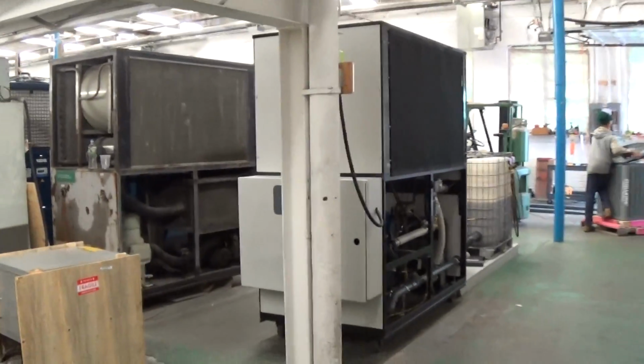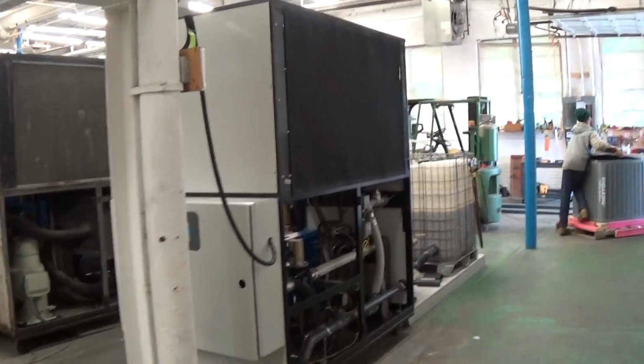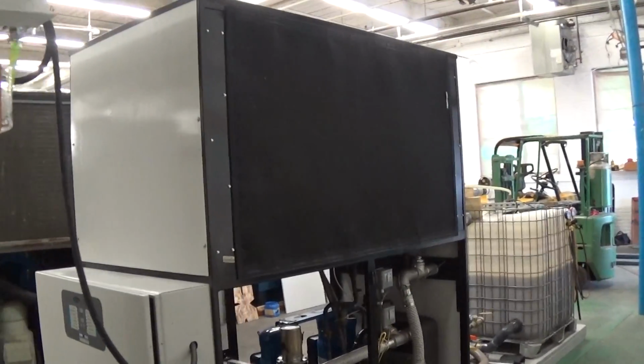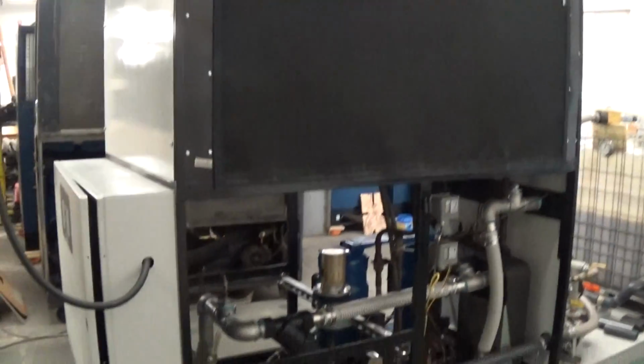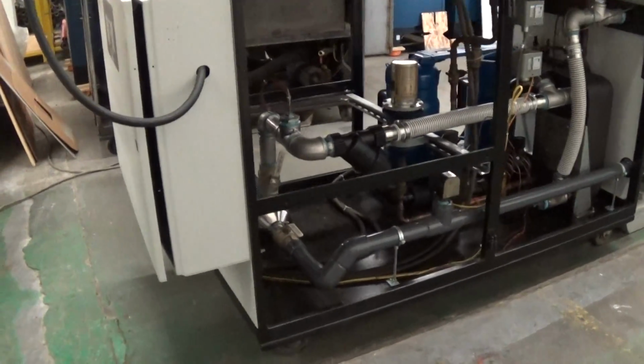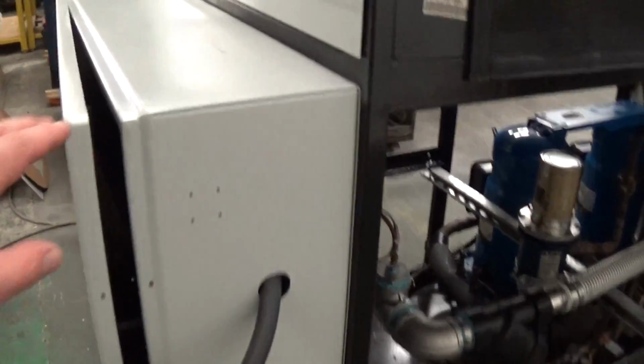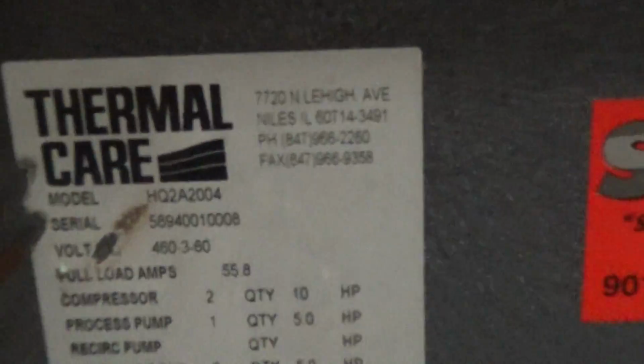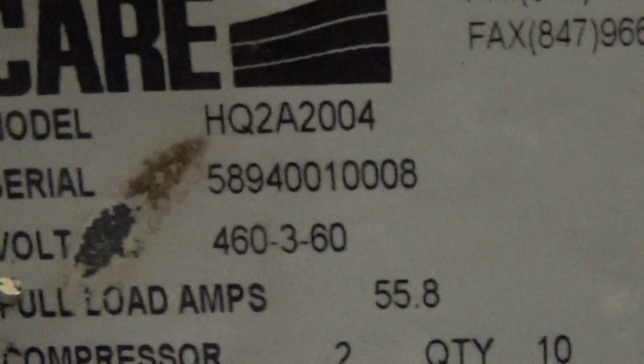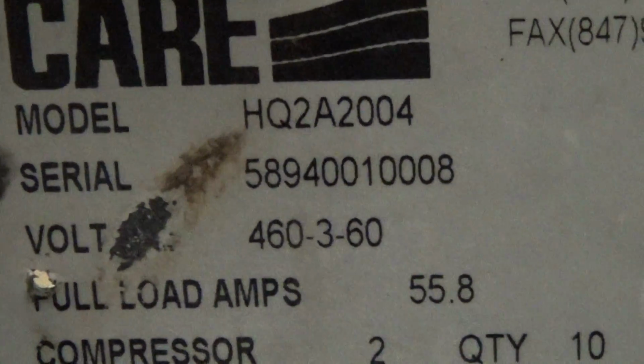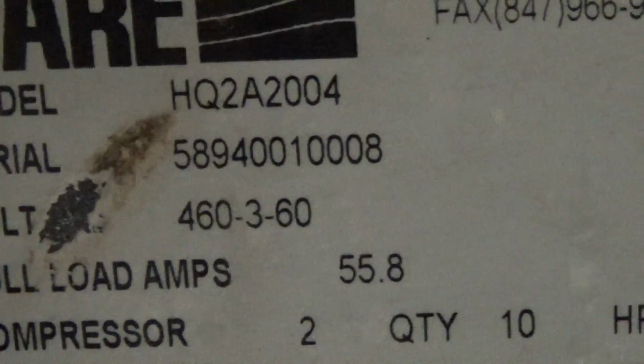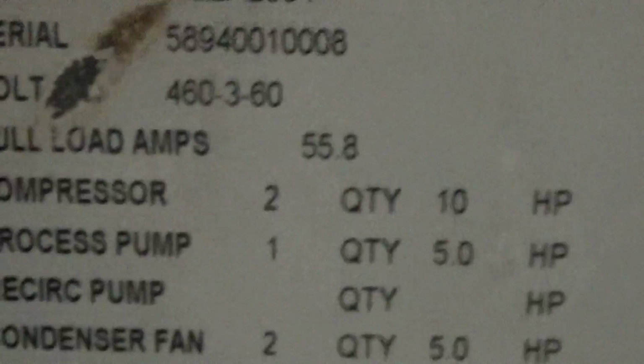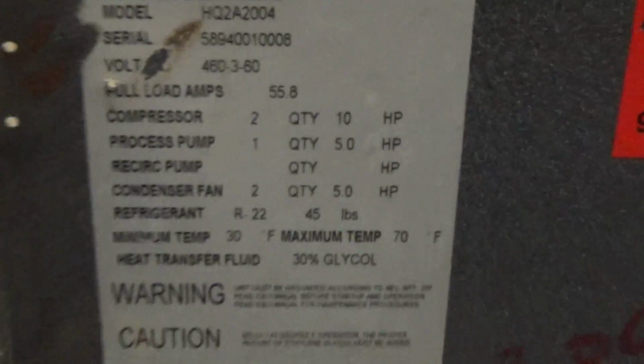It's May 24th, 2017, and today we're going to do a runoff of this refurbished ThermalCare 20-ton air-cooled chiller. I'm going to start by just opening up the cabinet here, showing you which serial number this is. This is an HQ2A2004, serial number 58940010008. It's a 460 volt 20-ton air-cooled chiller.